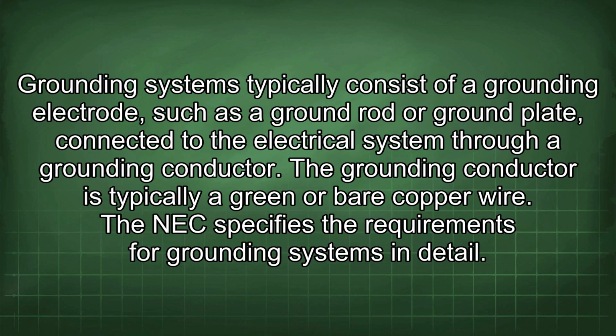Grounding systems typically consist of a grounding electrode, such as a ground rod or ground plate, connected to the electrical system through a grounding conductor. The grounding conductor is typically a green or bare copper wire. The NEC specifies the requirements for grounding systems in detail.